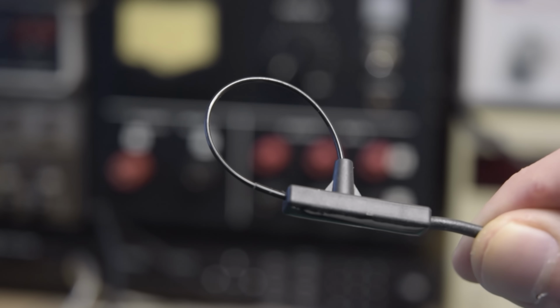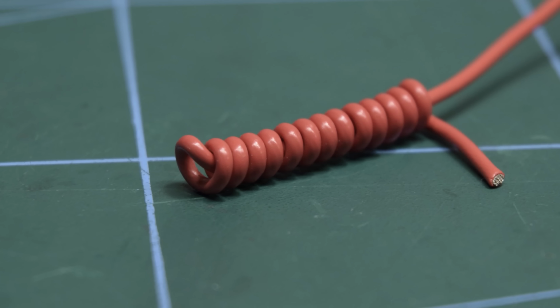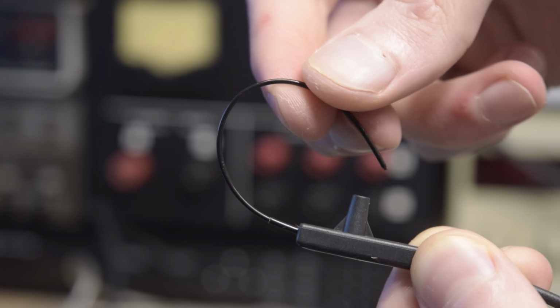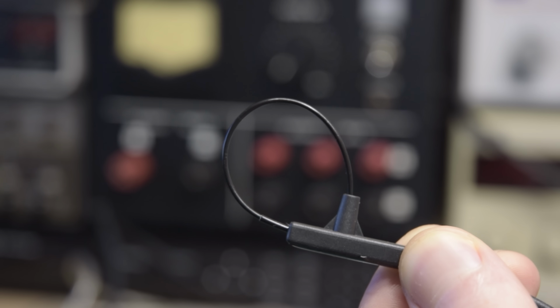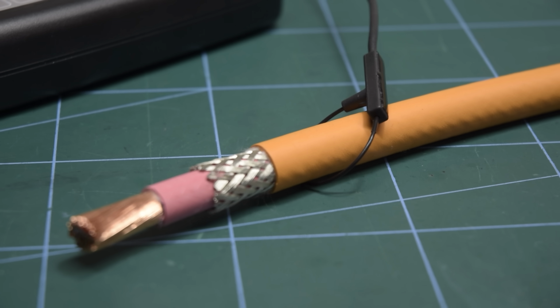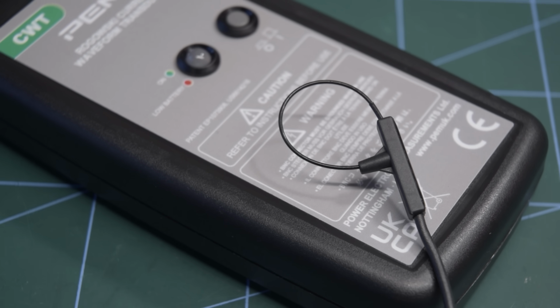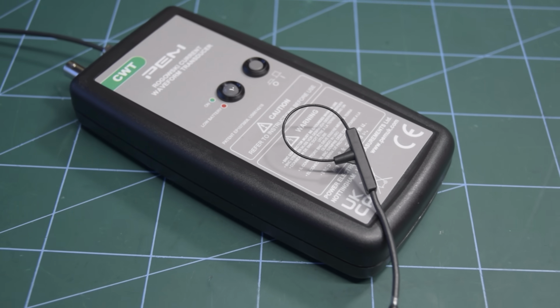A Rogowski coil is essentially a piece of wire wrapped around itself. When put into a loop like this, it will produce a voltage proportional to the rate of change of the magnetic field, or current, passing through it. This can then be integrated to provide the actual current, which is what goes on inside this box.